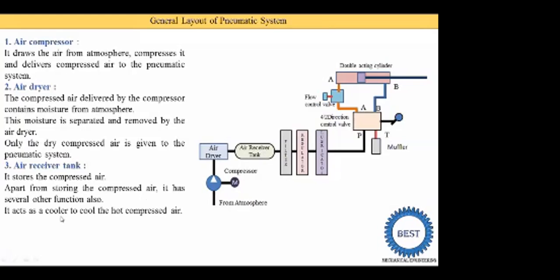First, it acts as a cooler to cool the hot compressed air. We know that during the compression process, as the pressure increases, the temperature of the air also increases. So when we store the air in a tank, its temperature is reduced. It also acts as a moisture separator to separate and remove the water content in the compressed air. When we store the air, the water content settles down inside the tank.